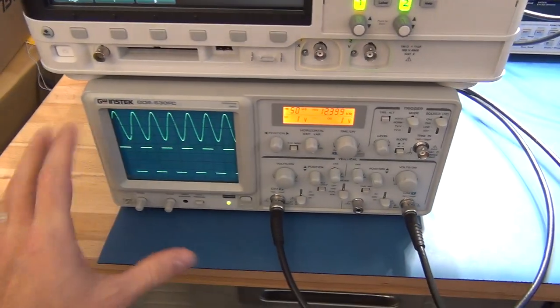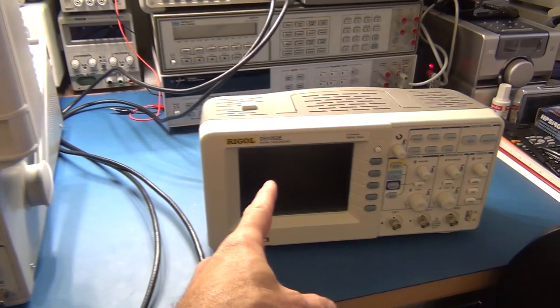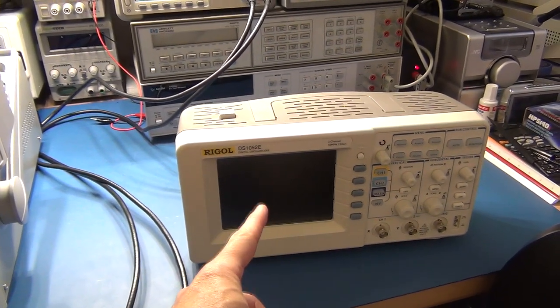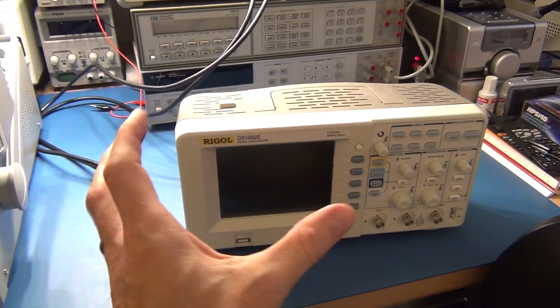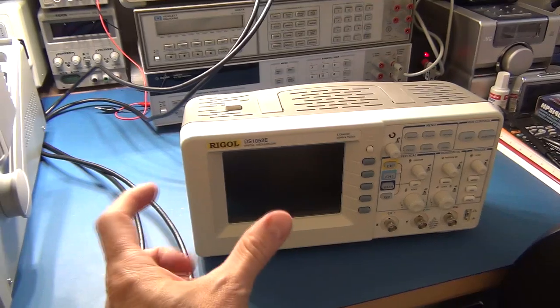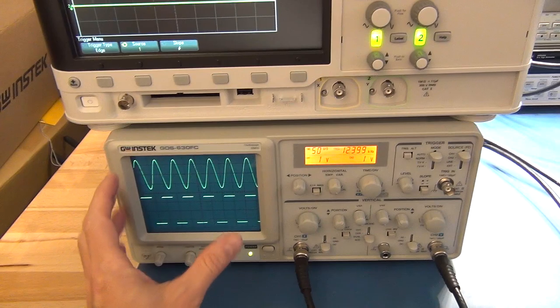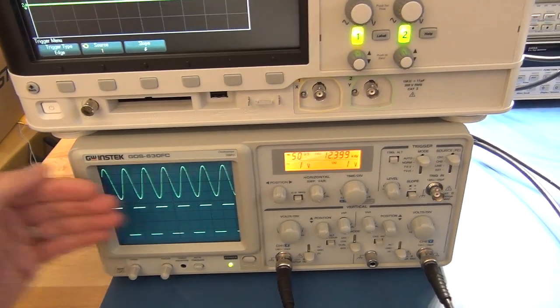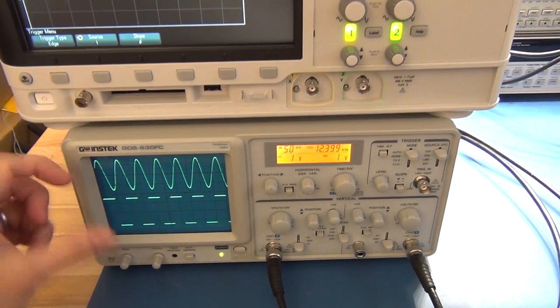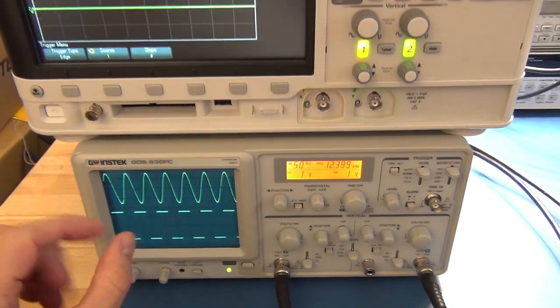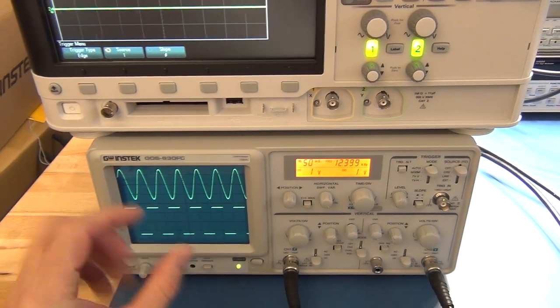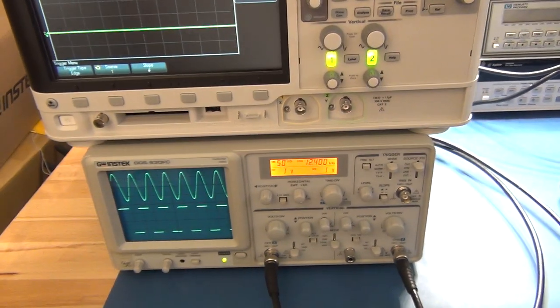However, that scope is operating at one giga sample per second but that's at its best performance. I've highlighted the issues with digital scopes - they're blind a lot of the time trying to process a signal. Whereas an analog scope for the most part is working real-time. The signal is coming in through an amplifier through a triggering system and it's being displayed real-time on your CRT. There are certain performance issues which I'm going to try and demonstrate.